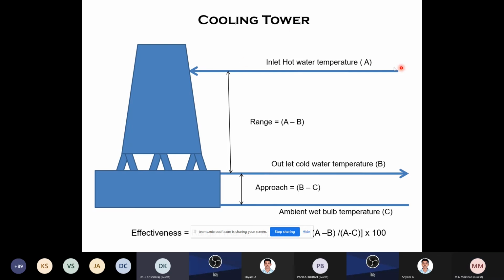So hot water is going in and cool water is coming out. The difference between A and B is called the range. How much range can you reduce? Range means how much of this variation the tower is able to reduce. Then the approach is the difference between the ambient temperature and the outlet temperature. B minus C is called the approach.